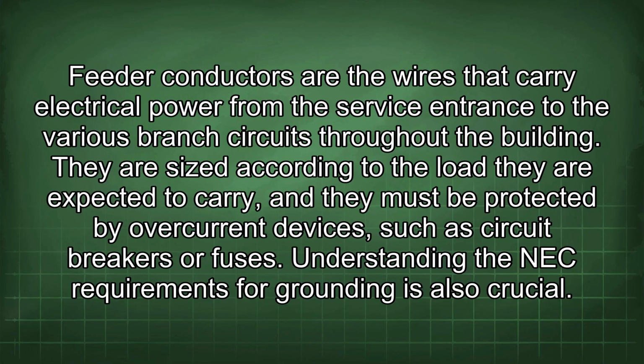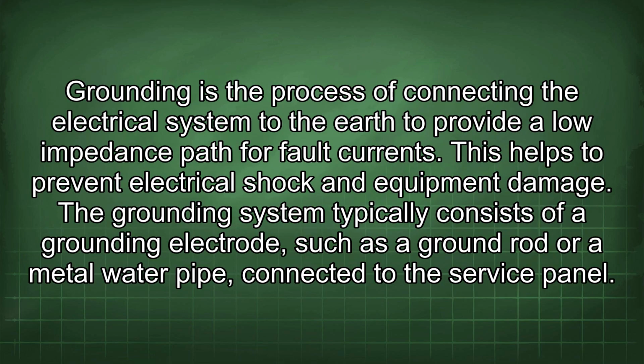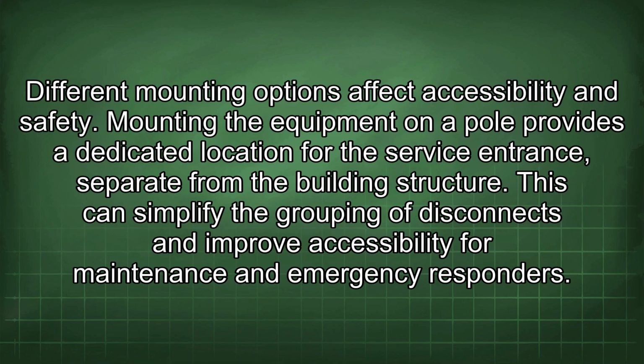Understanding the NEC requirements for grounding is also crucial. Grounding is the process of connecting the electrical system to the earth to provide a low impedance path for fault currents. This helps to prevent electrical shock and equipment damage. The grounding system typically consists of a grounding electrode, such as a ground rod or a metal water pipe, connected to the service panel. Different mounting options affect accessibility and safety.